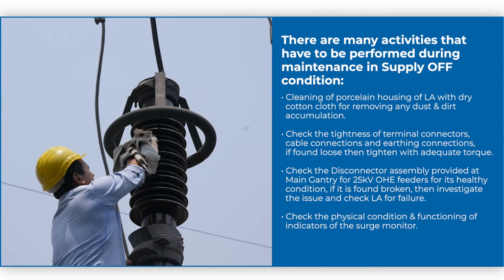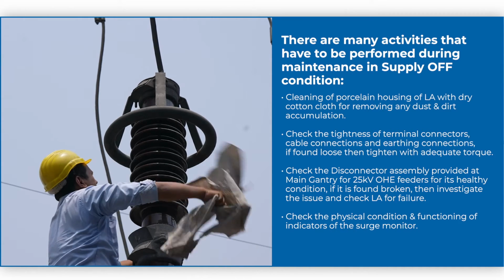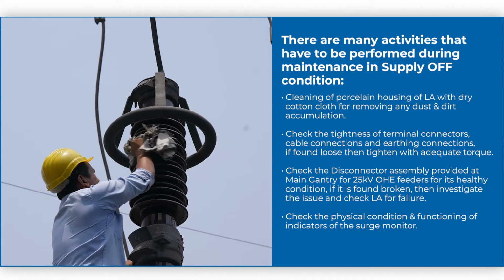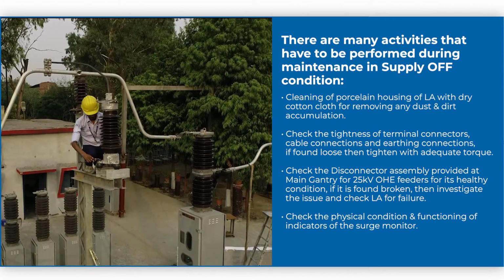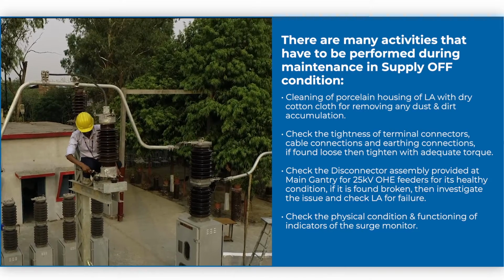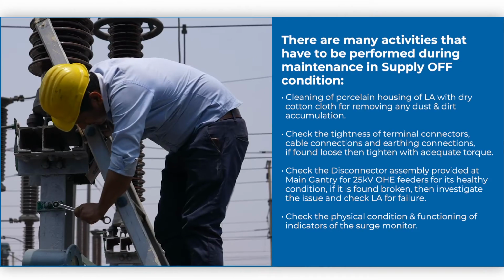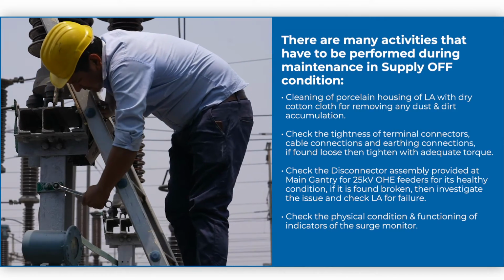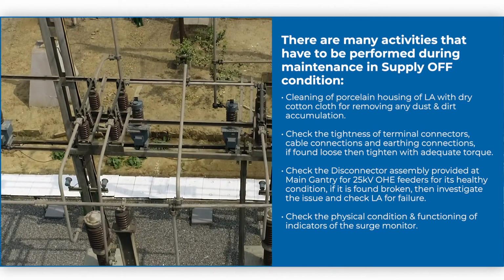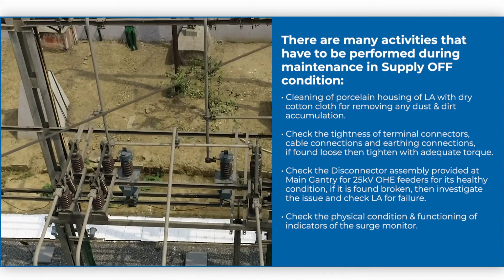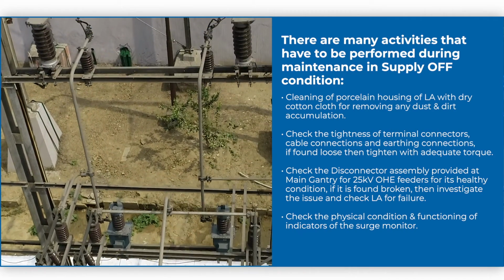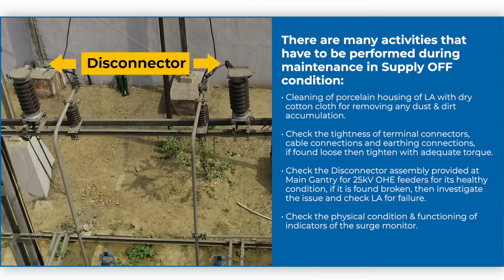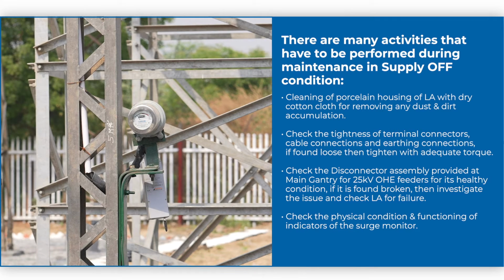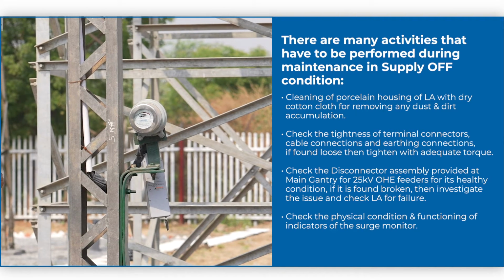Cleaning of porcelain housing of LA with dry cotton cloth for removing any dust and dirt accumulation. Check the tightness of terminal connectors, cable connections, and earthing connections. If found loose, then tighten with adequate torque. Check the disconnector assembly provided at main gantry for 25 kV OHE feeders for its healthy condition. If it is found broken, then investigate the issue and check LA for failure. Check the physical condition and functioning of indicators of the surge monitor.